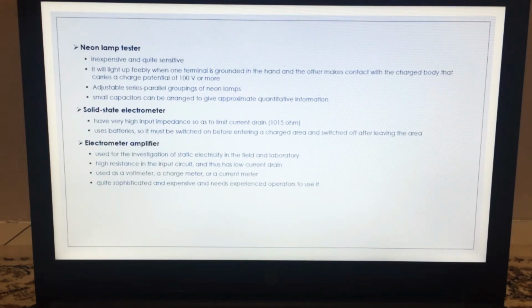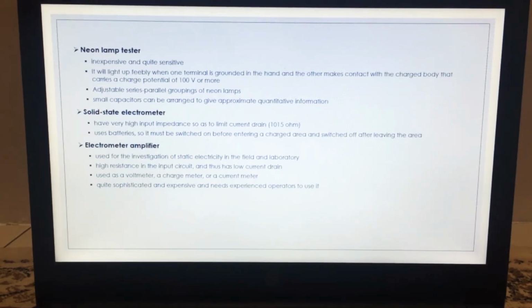The third one is the solid state electrometer. It has very high input impedance, 10^15 ohms, so as to limit current drain. It uses a battery, so it must be switched on before entering a charged area and switched off after leaving the area. And lastly is the electrometer amplifier, used for the investigation of static electricity in the field and laboratory. It has high resistance in the input circuit and thus low current drain. It is used as a voltmeter, a charge meter and a current meter. Quite sophisticated and expensive, it needs an experienced operator to use it.